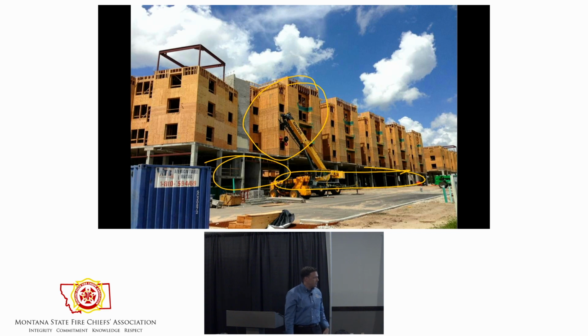Now, this building's going to have standpipes. Why? Because the standpipe rules look at it completely differently. It's the total height of the building, not buildings. Just know that there's a complete loophole. The bottom sprinkler system was called what? NFPA 13. Sprinklers everywhere. Upper is called what? 13R. It's Pirate's favorite one, right?